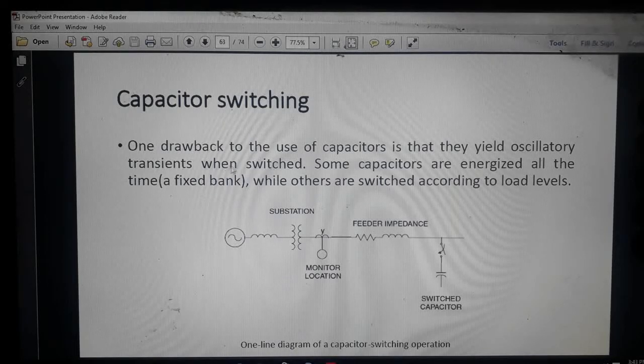A drawback to the use of capacitors is the oscillatory transient when switched. Some capacitors are energized all the time while others are switched according to the load level.